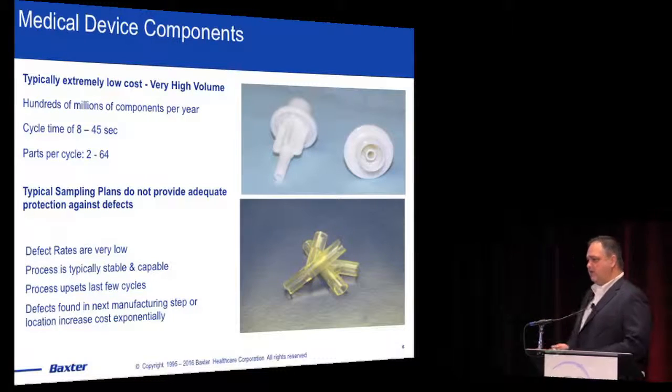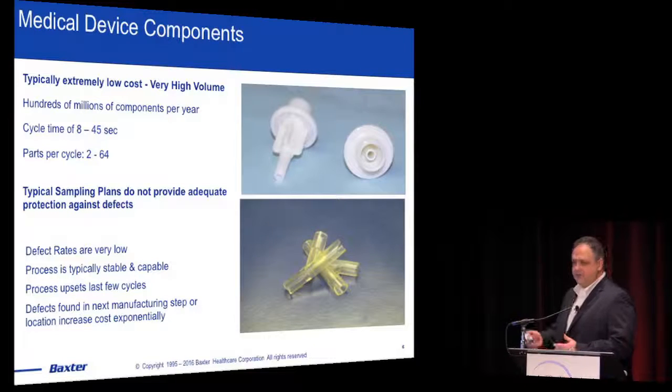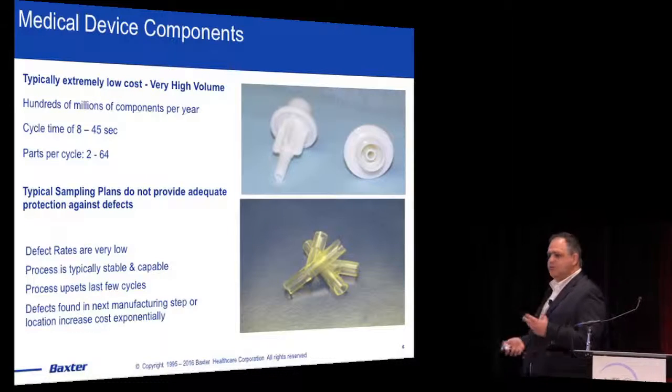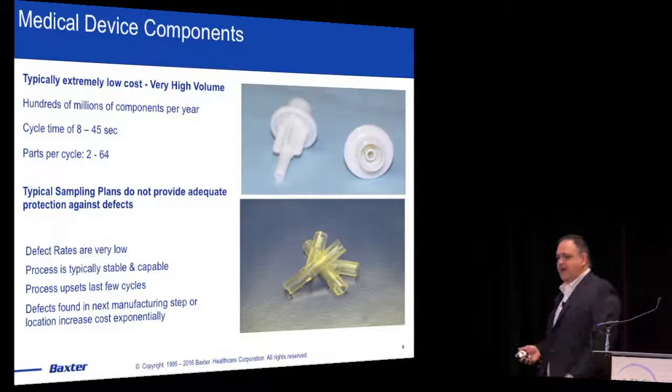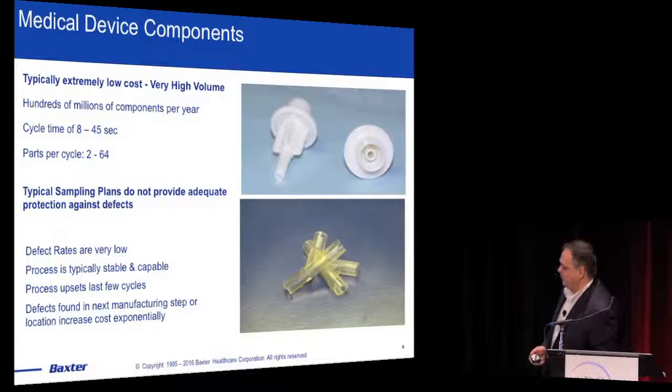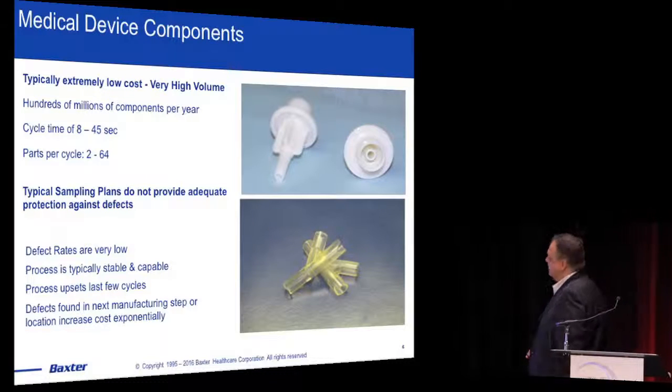We've also been able to prove over the years that a typical sampling plan that most medical device companies would use is not very effective in detecting defects at that production rate. Things will look fine and your customer will call you and say, hey, we just found something, let's go have a recall. That's not something you like to do. Like you mentioned earlier, recalls want to be avoided at all costs.